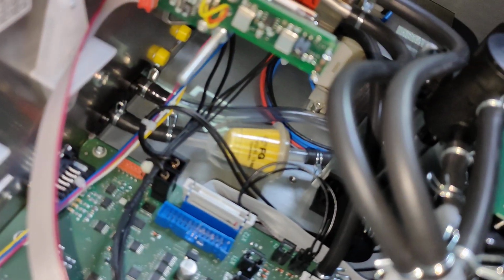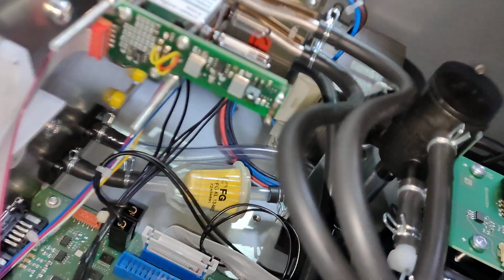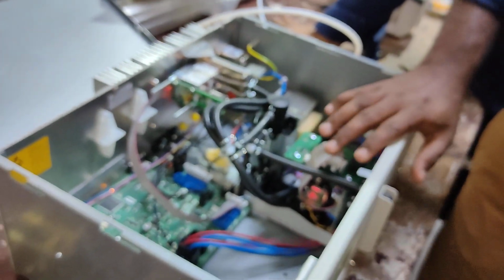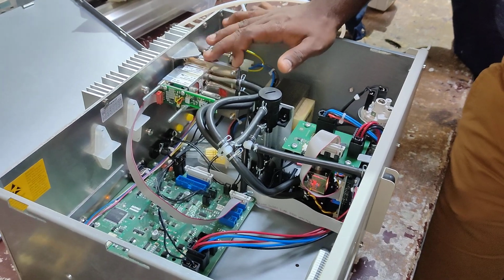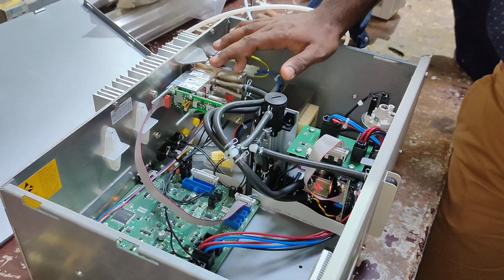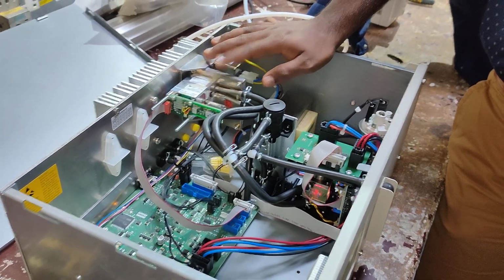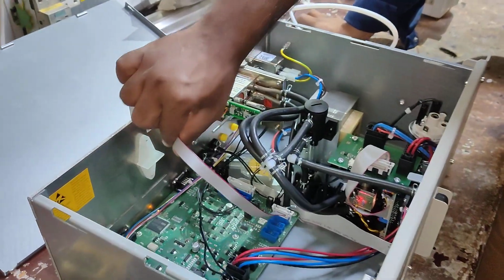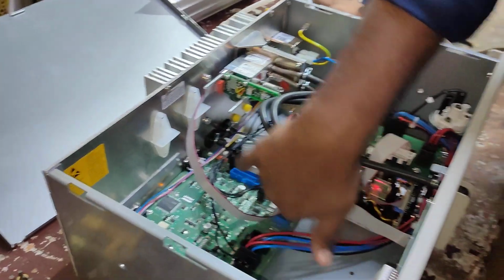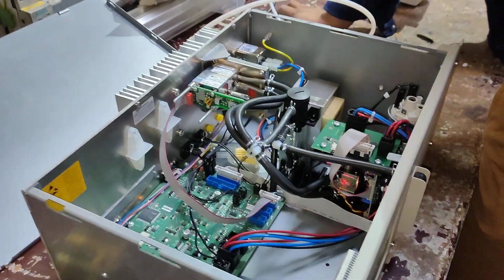So what is this heat sink they have put outside? This one? Yeah. Because this cell will be heated at around 40 degrees C, so they want to retain that temperature. Because the IR absorbance is more dependent on the temperature of the cell, we are heating this cell. This detector is getting heated up with the power from here, so we will heat it up until 40 degrees.